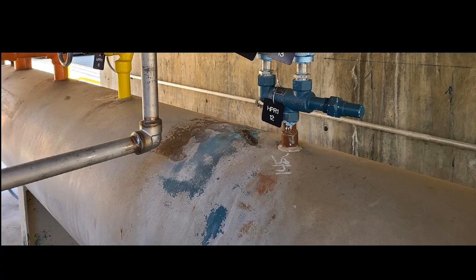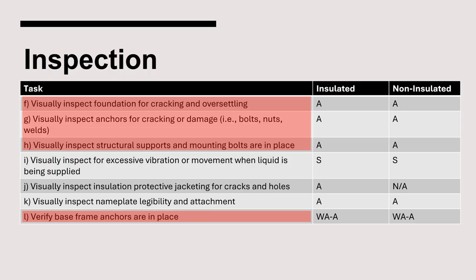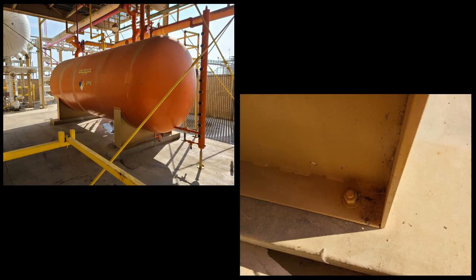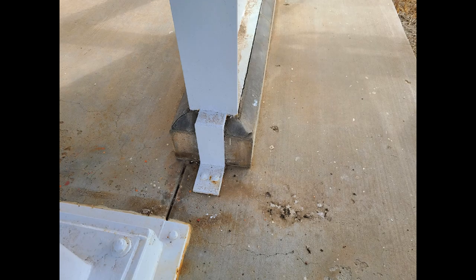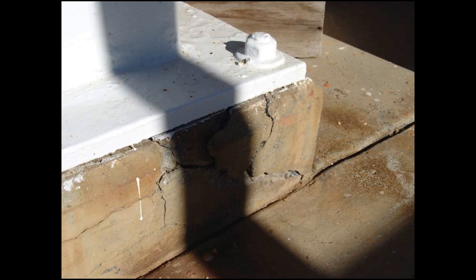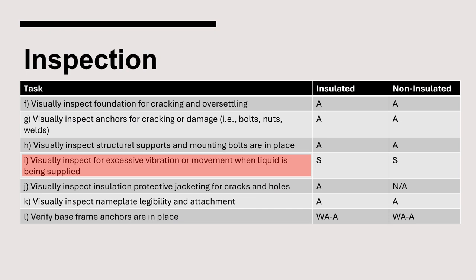Here is an example of minor paint degradation. The next set of requirements pertain to the vessel foundation, anchorage, and supports. Typically, high pressure receivers are ground-mounted with anchor bolts embedded into the concrete foundation; special attention should be made to ensure the foundation is not cracking. IIAR 6 also requires semi-annual inspection of the vessel for excessive vibration or movement when liquid is being supplied to the vessel. This requirement is most relevant to surge drums that receive liquid through a solenoid valve; for HPRs, the high pressure liquid supplied by the condenser should not be a cause of any vibration.